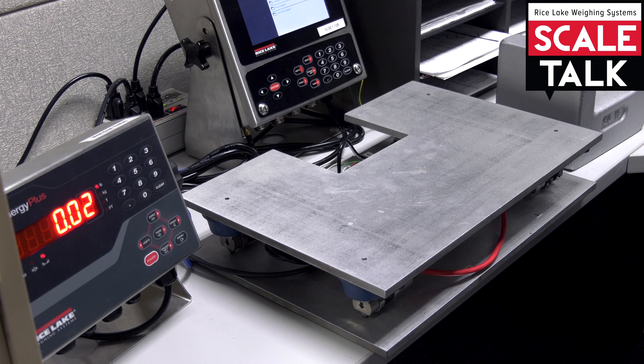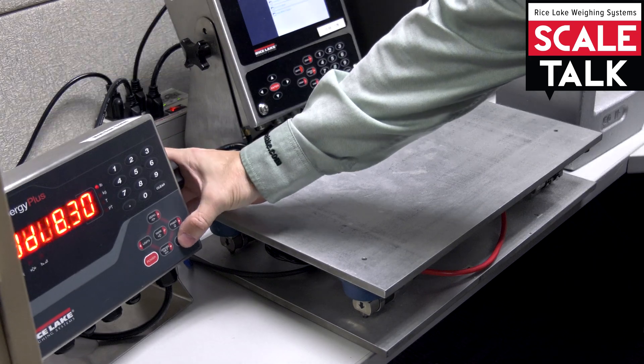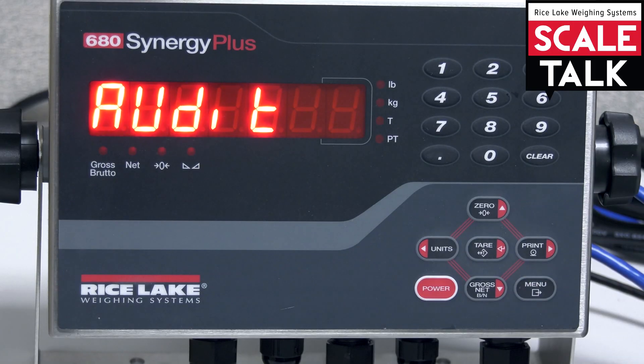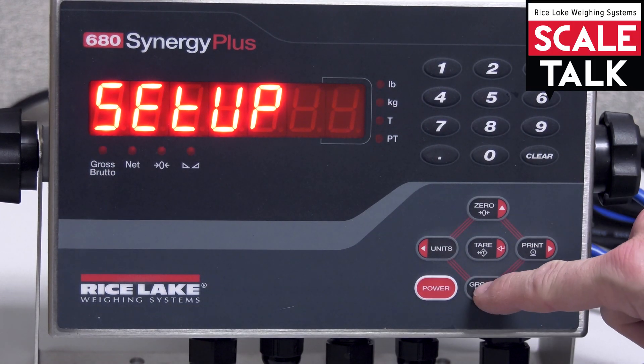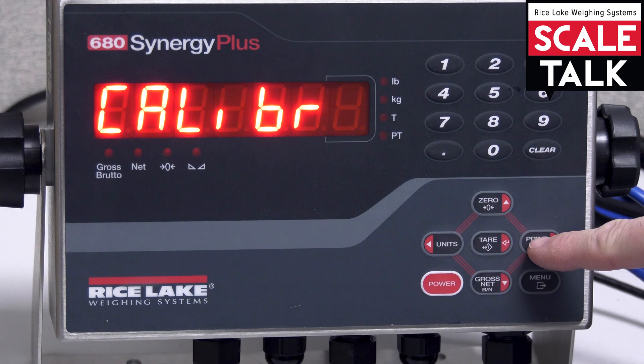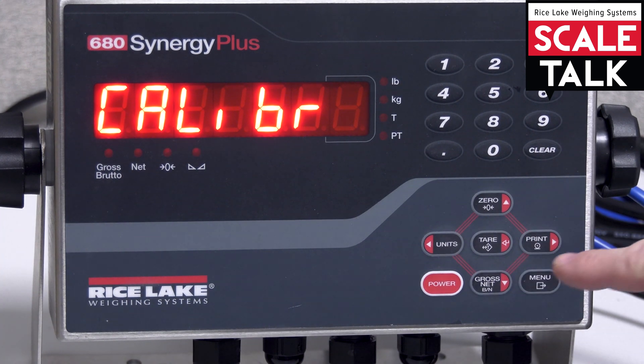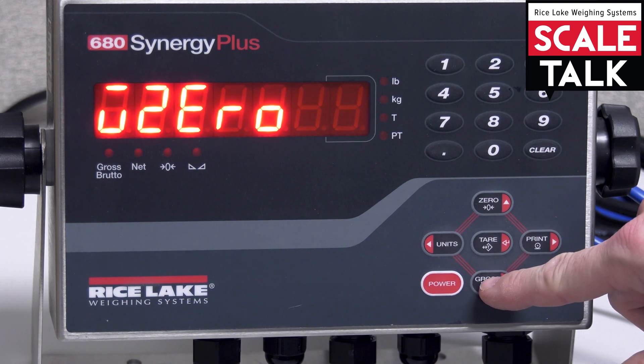We're going to start with a zero calibration, so I'm going to hop into the menu here quick. And I'm going to come over to calibration and this first step that I see is a W0.